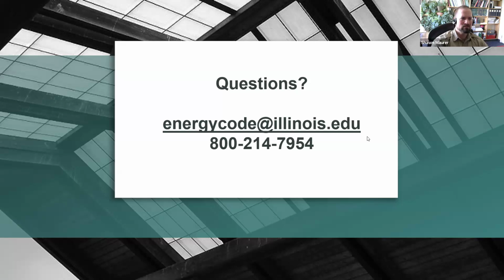As far as controlling for other spaces like an equipment room, that qualifies as a separate space that doesn't have to meet the provisions of the envelope for the energy code. A data closet is within the larger building. There's no specific requirements in the code for a data closet at this time, but there are data closet units in the efficiency tables, as far as types of mini splits, things like that, and I believe there are efficiency requirements that have to be met for those types of units.